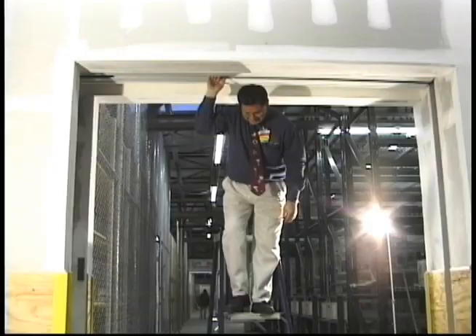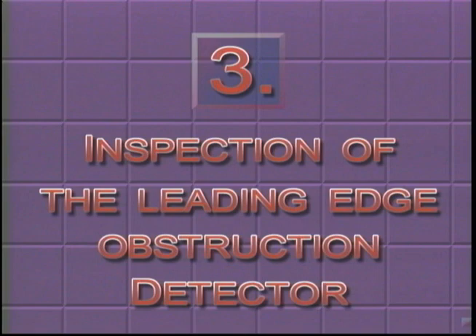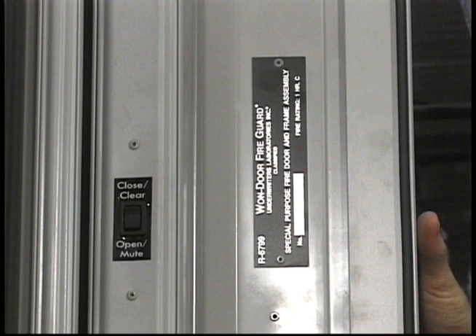The final preventative maintenance item is the inspection of the leading edge obstruction detector. This part is the aluminum cap on the leading edge of the door assembly. Sensing switches are located behind this cap which are connected to the microprocessor. This edge cap should be firmly attached to the lead post assembly of the door and installed so that the only movement is for the activation of the sensors as shown. If this edge cap is loose or improperly aligned, consult the Won-Door customer service department to schedule a service call.